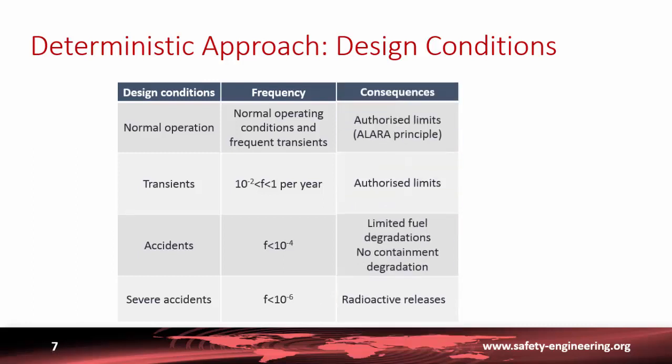Regarding the consequences of these design conditions: in normal operation, consequences should remain within authorized limits, as there is regulation about the amount of radioactivity that can be released, and using the ALARA principle, everything should be done to reduce this release as low as reasonably practicable. For accidents, there could be some limited fuel degradation, but the containment should remain completely leak-tight and no degradation is allowed.